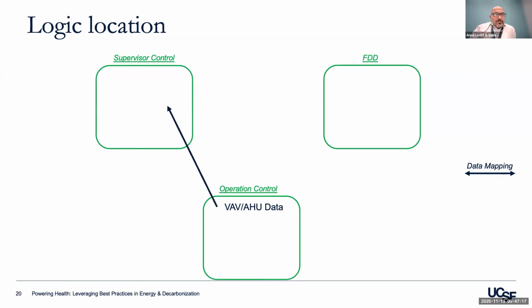But what usually happens is you're passing data, even within a controller, from a VAV or an air handler. It gets pushed up into the operation logic. The operation logic runs and makes a decision for a reset, and that gets pushed back down into set points, like supply temp set point and supply pressure set point, among others. But it really is logic that can be separated out—it doesn't need to exist within the same controller. Understanding that helps you determine whether this is the best way to deploy and maintain this logic.